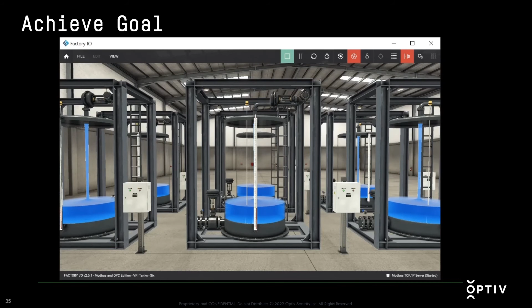And if it loses comms, or the attacker doesn't get paid within a certain time frame, they set detonate all, and that's exactly what's happening here. It's just going to continuously fill until an overpressure exists. Again, that PLC situation would be a denial of service on any type of mechanisms that are there to control this.